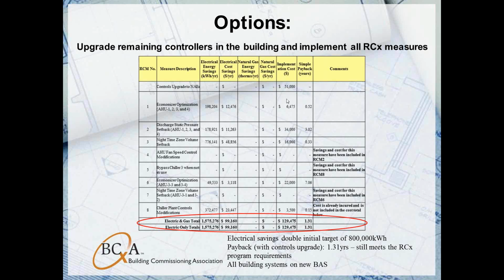So to go forward with option 2 here, we're able to get our full electrical savings, which is double our target, and we're able to still meet the 1.5 years or less payback here. So we're basically getting a full building controls upgrade for under a 1.5 years payback. And a big benefit is that all of the systems in the building will be on one BAS, and it'll be on the BAS that's the campus standard. We can connect this to the campus's extended architecture, and the functionality will be a lot greater.